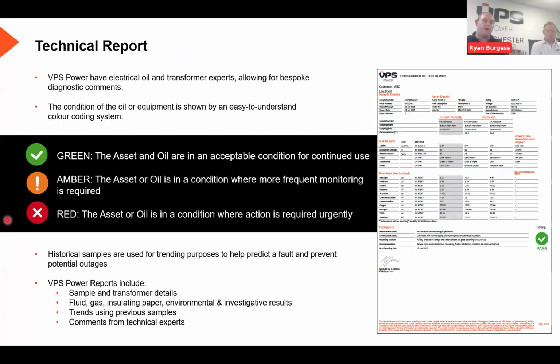So here at VPS, our reports follow a basic traffic light system. A green indicator on the report shows that the fluid quality, the paper insulation, and the asset itself from the gases point are in an acceptable condition, and you don't need to take any further action other than whatever you've got planned for another year or 2 years, whatever your sampling period is. Then we have an amber, also known as a caution. At that point, that shows that the asset and the fluid are still in an operable condition, and you're still able to operate them, but you may need to lower the load, resample more often, maybe do some maintenance of some form to help return that situation back to a good or a pass. But again, it's still usable.